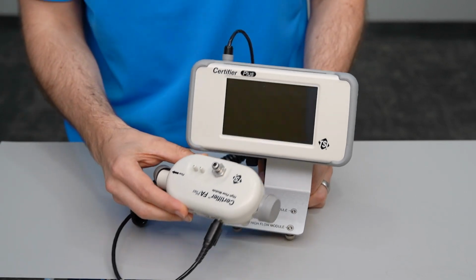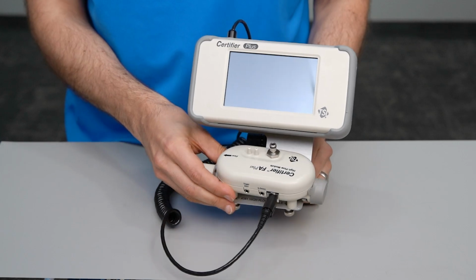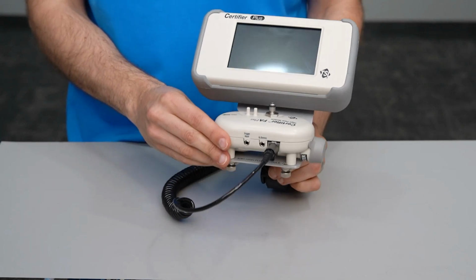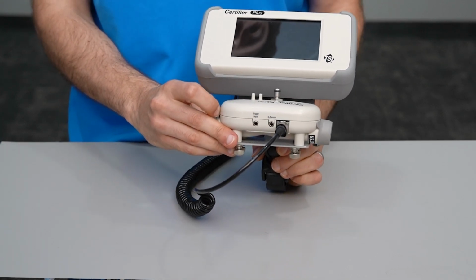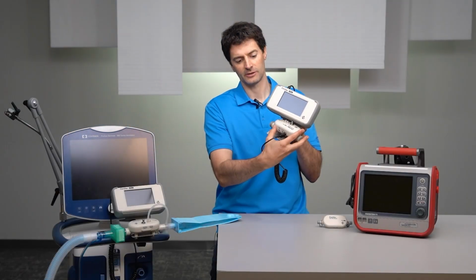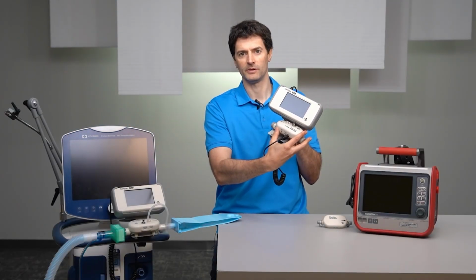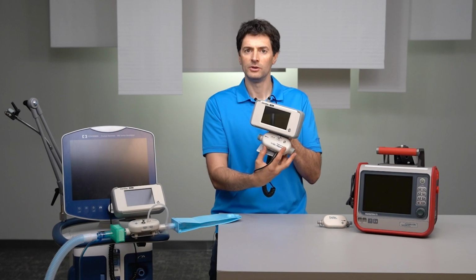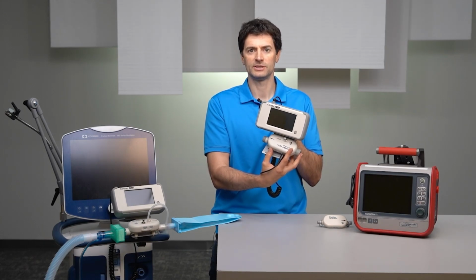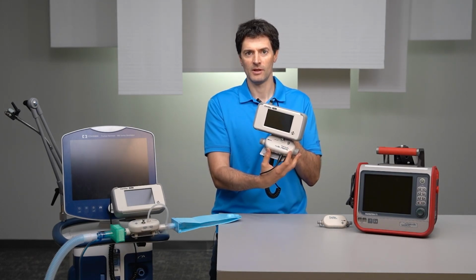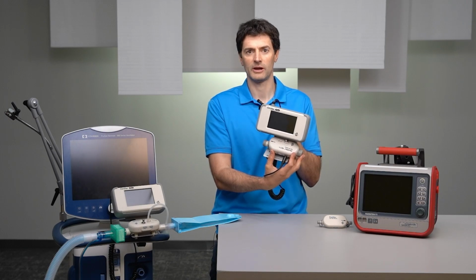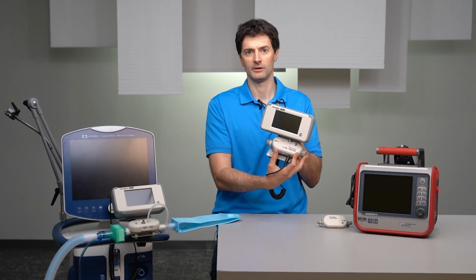Some biomeds prefer to have the flow module mounted upside down in order to allow for greater access to the connectors, which are located on the top of the flow module. Note, however, that in this upside down orientation, that would flip the flow direction as measured by the module. And so this would need to be accounted for when attaching the ventilator tubing.